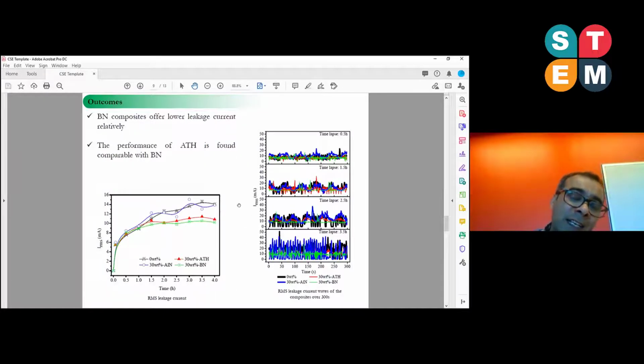So here's the leakage current. The leakage current is directly correlated with the tracking and erosion, because leakage current creates different hotspots on the insulation, and once the temperature increases at the hotspot during dry band arcing, that dry band arcing can easily deteriorate the insulation and start electrical tracking. So we have to continuously measure the leakage current on the surface of the insulator. We measured the instantaneous current over a 5-minute period, around 300 seconds, and then calculated the RMS current.